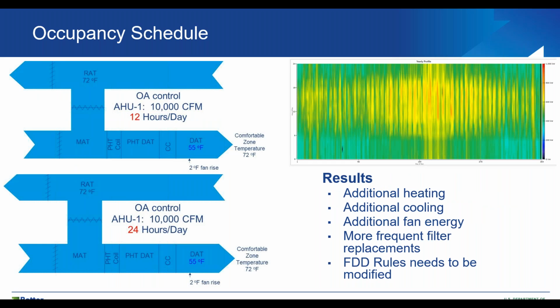So here's an example of that same air handling unit, if it's operating 12 hours a day, for example, assuming it's operating normally. And on the right, you'll see this is a yearly profile. If we're looking at a normal flag, you can see the yellow indicates pretty much when the system turns on in the morning and when it shuts off at nighttime. And then it doesn't have much weekend use. There's a little additional usage in the summertime due to additional cooling. But the flags would be, okay, how many days is it left on? So about 3/4 of the way across, you can see there are times that the air handlers were left on beyond their normal hours of occupancy. So the rule would flag when those times occurred.